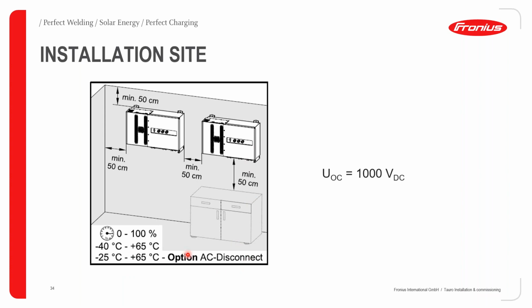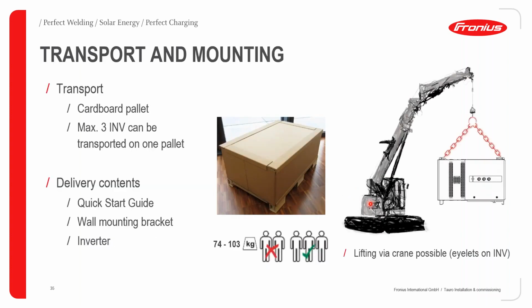If you are going to order the Tauro with the AC disconnect, please make sure that the minimum temperature will change from minus 40 degrees Celsius to minus 25 degrees Celsius. Again, please take careful attention to the maximum open circuit DC allowed per string, and that is 1000 volts DC.